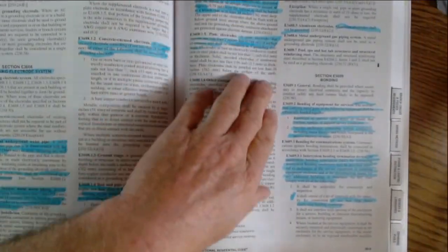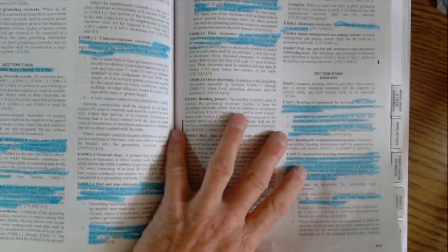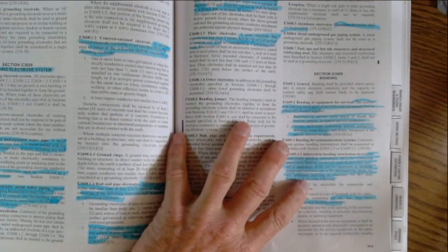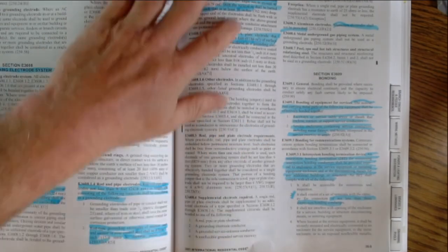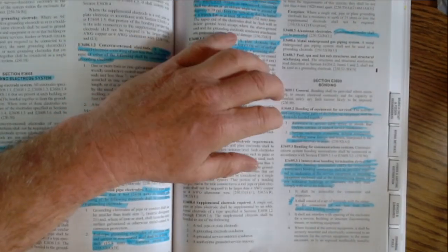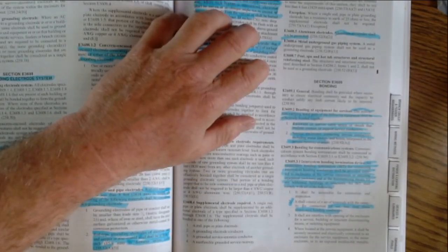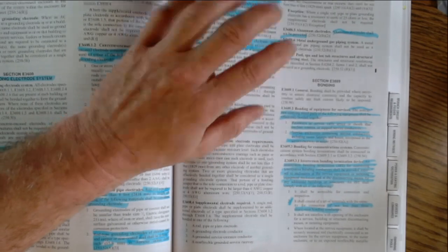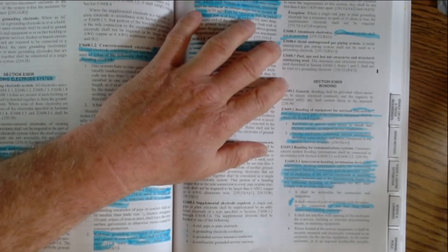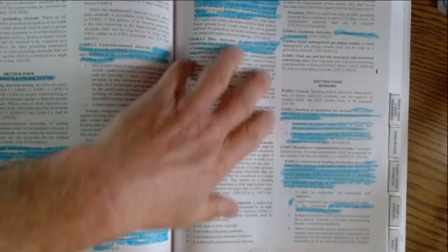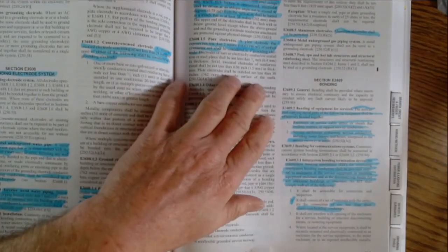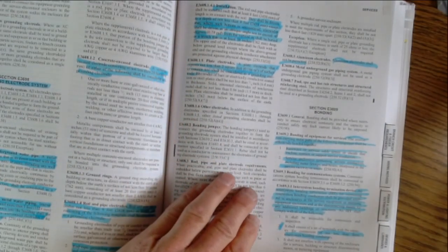Pools. Okay, had a question: swimming pool bonding. They had the enclosure of the light. They had the stairway in a pool. They had, what was the other option? Can't remember. And then they had like a towel rack somewhere, a metal towel rack. The answer was the metal towel rack didn't need to be bonded because the other ones were all within a certain distance of the pool or within the pool. So that's how you figure that out.